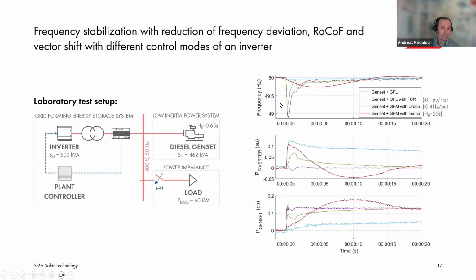And what do we see on the right side? These are the responses: in frequency on the upper side, the active power response of the inverter, and also the active power response of the diesel generator, which represents the grid. We see that in the grid following case, the frequency deviation is quite high, and the rate of change of frequency is also very high. Afterwards, the frequency is restored by the diesel generator and its secondary control mechanisms.